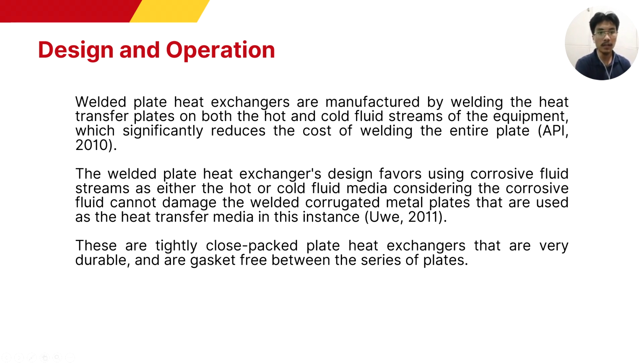Next, these are tightly packed plate heat exchangers that are very durable and gasket free between the series of plates. Again, the gaskets between the series of plates are non-existent because the plates are welded, which significantly reduces the cost of the entire equipment. Also, this results in a much higher temperature and pressure resistance. So the welded plate heat exchanger can be operated in environments with very extreme conditions or settings that have very high temperature and pressure.